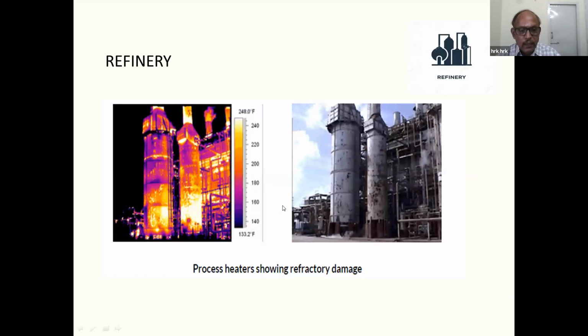thermography in a refinery is process heaters, where you heat the crude oil for further processing. There will be a burner where fuel is burning, and inside the insulated jacket there will be a coil in which the crude is circulated. If there is any refractory failure, then we will lose a lot of heat, and that may lead to an accident also, which we will see later. There may be excess heat radiation on the tube that may lead to accidents. These things we can find out from the thermal imager by taking thermography periodically, and we can take corrective actions and prevent major accidents.